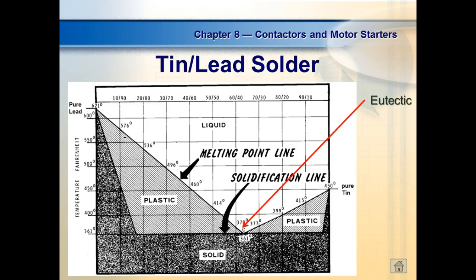As soon as it drops down below 361 degrees, it turns into a solid. Now, this is called eutectic solder. It's actually 63/37. 63/37 is eutectic solder. If I get those two ratios between tin and lead, it has no plastic state. So these heaters over here, once they get that little rod up to 361 degrees, it does what? It turns into a liquid, and it allows it to do what? Spin and kicks over. But the problem with these is the temperature might get up in the heater.